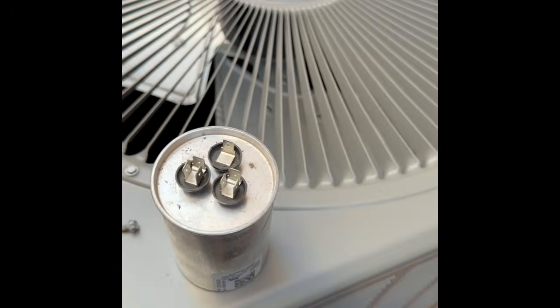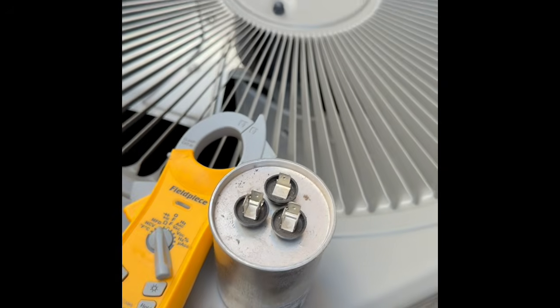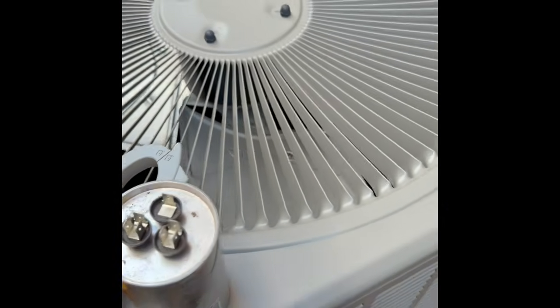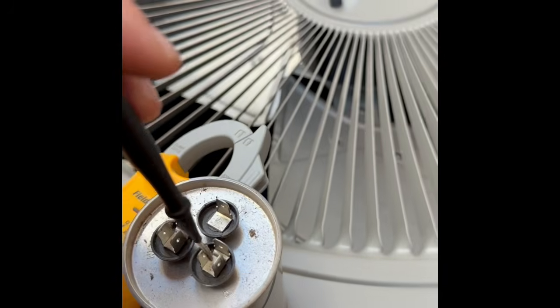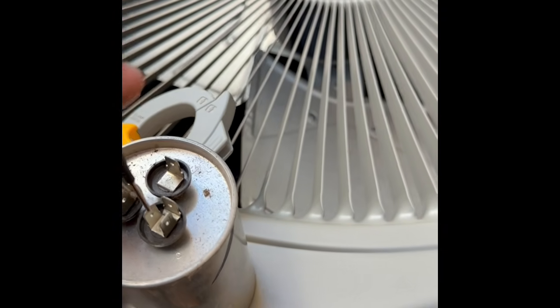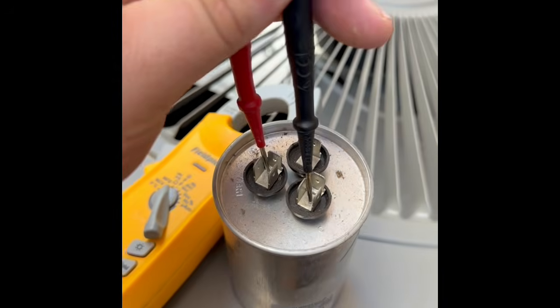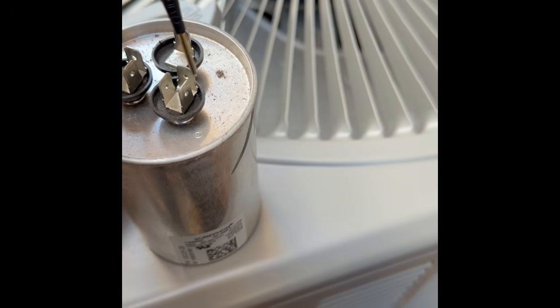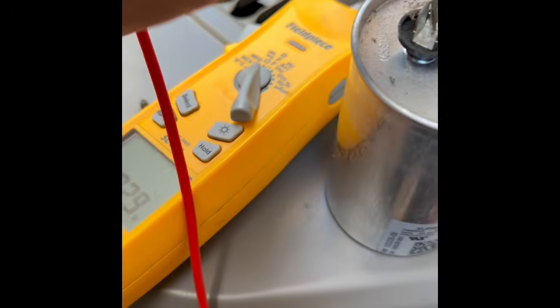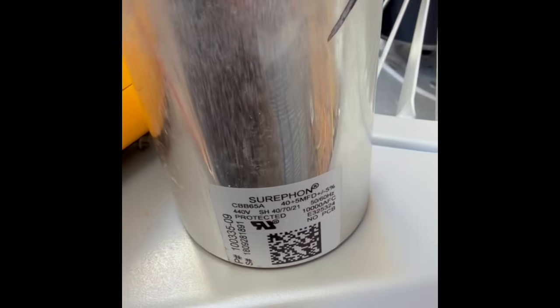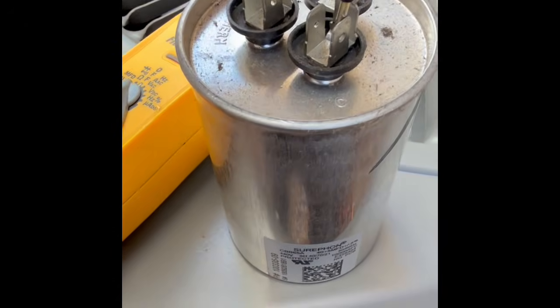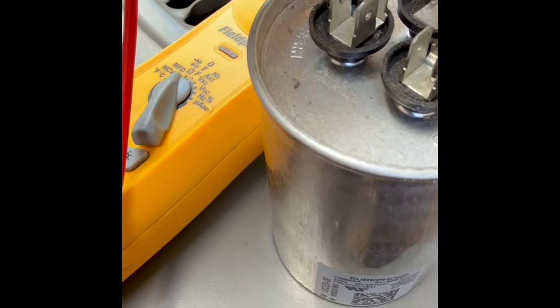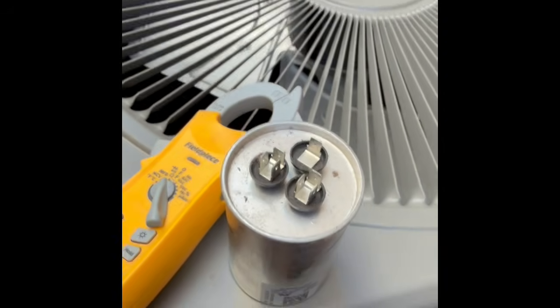Set our meter to microfarads. Grab our leads. And we are going to test from common to Herm. And we got 37.28. And that's out of 40. And on the fan side, so we'll go common to fan, we got 4.7. So, with that being said, this capacitor is considered failing according to the manufacturer's specification.